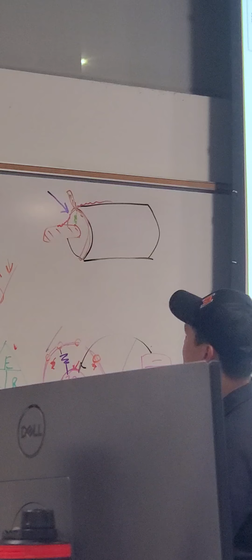Such products exhibit long creepage paths, dimension size, and the unwanted surface leakage resistance can cause defects. So this is when the guard terminal can enhance the accuracy of the measurement. By using the guard terminal to perform a 3-terminal test, the surface leakage current can be ignored. We take this unintended path and literally take it out of the equation. So then components are charging current, absorption current, conduction, or leakage current - this is what's taken out. Surface leakage would need to be excluded if just the insulation resistance measurement of the material is required. It's done using the guard terminal, which is available on most testers, like this one here.